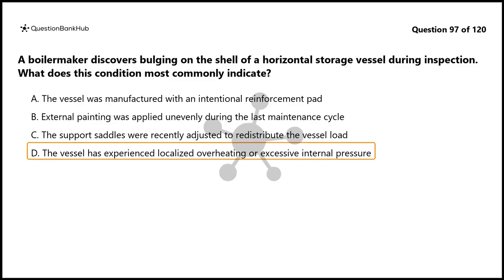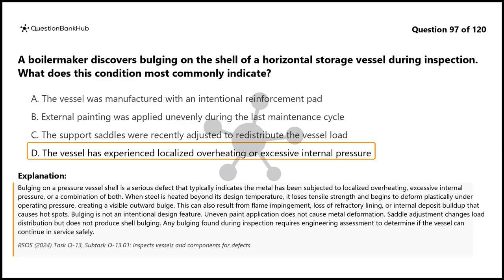The correct answer is D. Bulging on a pressure vessel shell is a serious defect that typically indicates the metal has been subjected to localized overheating, excessive internal pressure, or a combination of both. When steel is heated beyond its design temperature, it loses tensile strength and begins to deform plastically under operating pressure, creating a visible outward bulge. This can also result from flame impingement, loss of refractory lining, or internal deposit buildup that causes hot spots.